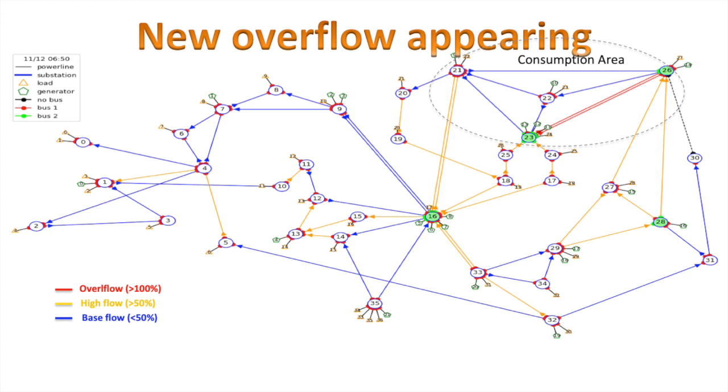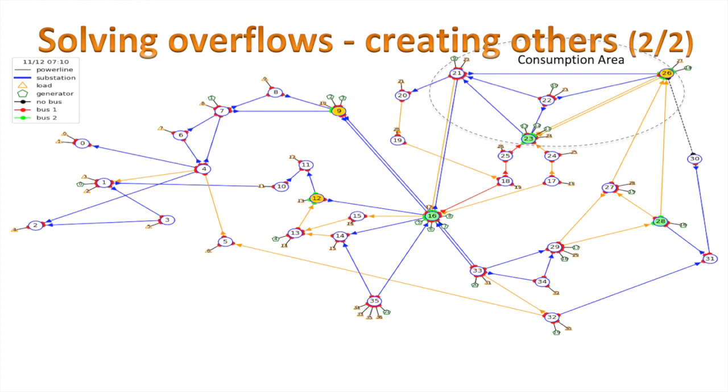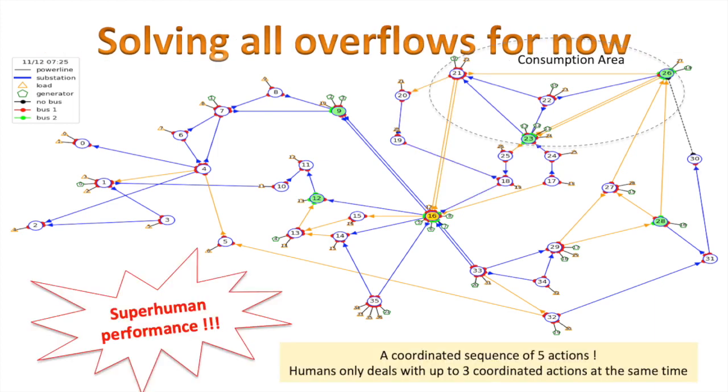45 minutes later, at 6:50 am, a new overflow appears because the consumption is increasing. A first new configuration at substation 23 solves it, but recreates the initial overflows. An additional sequence at three substations solves those overflows, but again creates some new ones in the other corridor. Finally, a last action at substation 16 solves it at 7:25 am. A sequence of five actions was temporarily needed, and this demonstrates some superhuman performance, because operators usually only deal with up to three coordinated actions at the same time to try solving an issue. This was quite a remarkable move from the agent. This is a demonstration that AI can help augment operators' knowledge about grid flexibilities on the way towards an assistant.